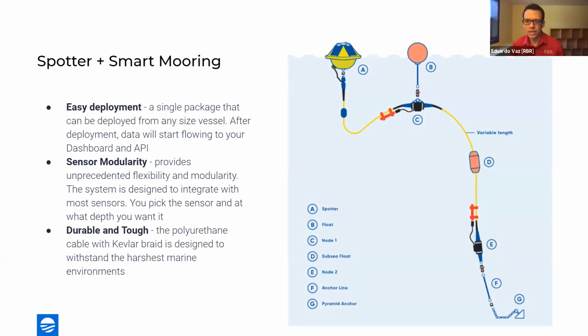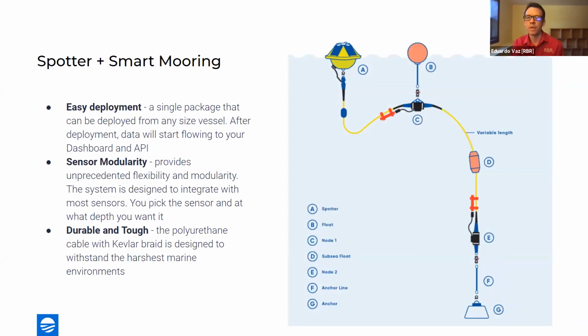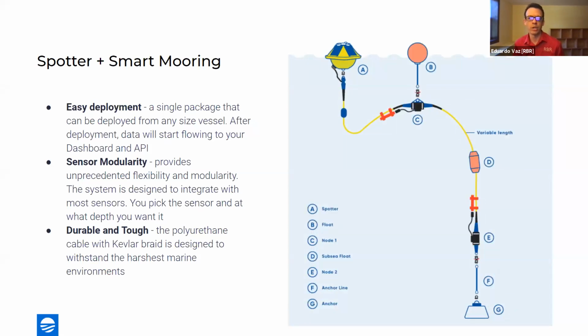Well, just to add to the biofouling and calibration schedule, in terms of the sensors that we're integrating, if that answers part of the question, Sean: for the Coda series, we expect that they remain within spec for a year. So we generally recommend an annual calibration of the sensors themselves. And that's beyond any kind of wiping of biofouling, as Sebastien mentioned. So that would be good to take into account as well if you have any of our instruments.